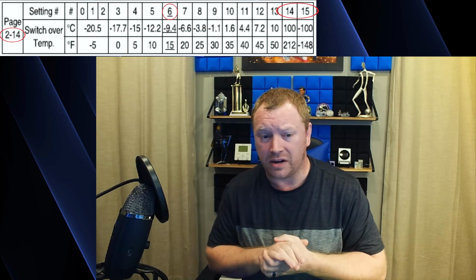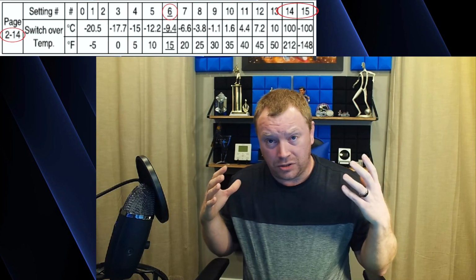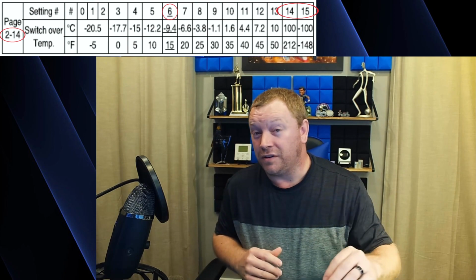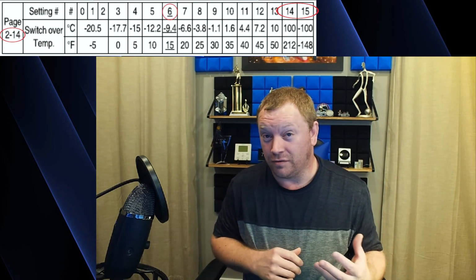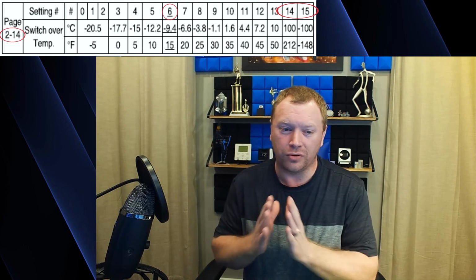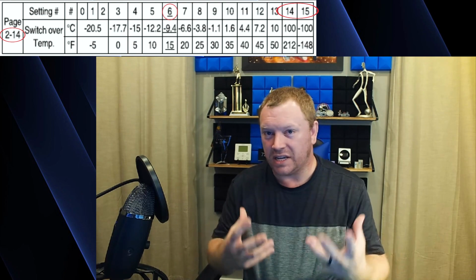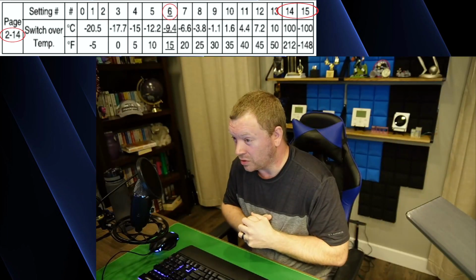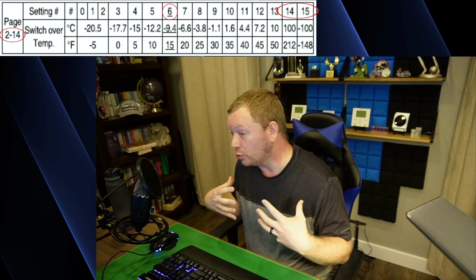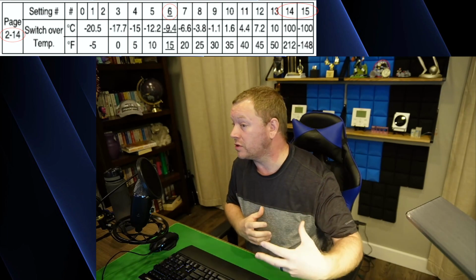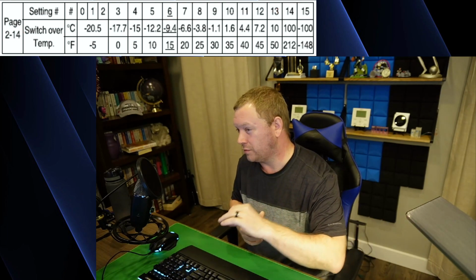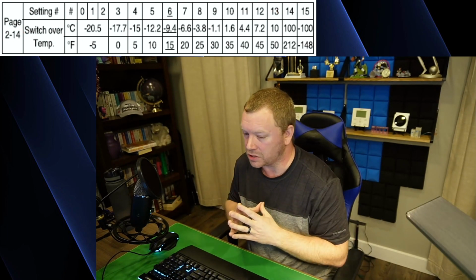Because if you're going to lock it out at 212 degrees outside, that's basically always going to be locked out. If you go to option 15 and that is minus 148 degrees, then basically that's saying, hey, you're going to run the heat pump all the time. So those are your ways of doing any testing, or sometimes we'll have folks that want to use a VRV system for cooling only and they want to run the gas furnace all year. But that's what options 14 and 15 mean when you look up at this chart here.